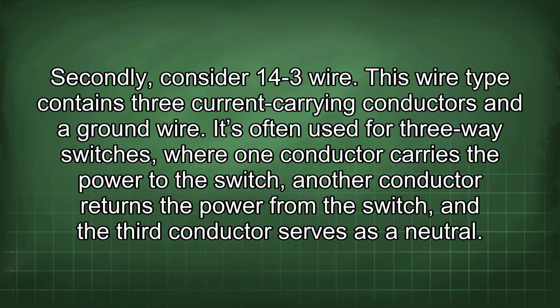Secondly, consider 14-3 wire. This wire type contains three current-carrying conductors and a ground wire. It's often used for three-way switches, where one conductor carries the power to the switch, another conductor returns the power from the switch, and the third conductor serves as a neutral.